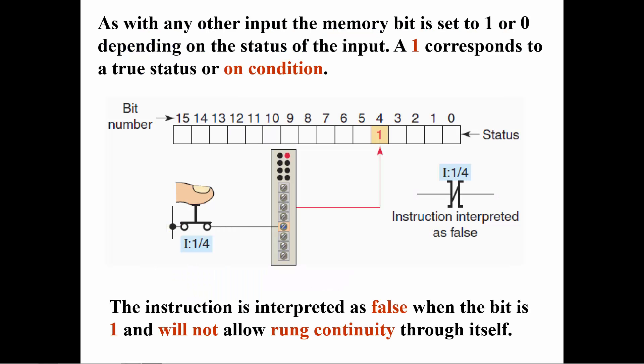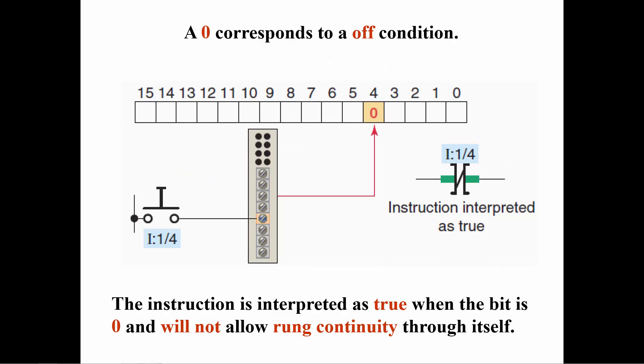The examine if open instruction behaves very much like a normally closed relay contact. When an external switch is closed, a 1 is placed at the address of the switch in the input table, and the examine if open instruction becomes false and will not allow rung continuity, much like a normally closed relay contact will not allow current to flow when its coil is energized.